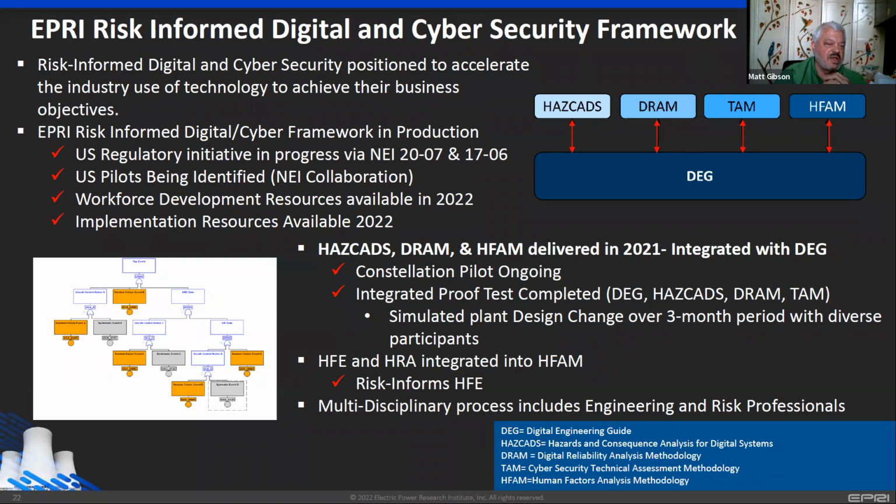Matter of fact, 17-06, which allows IEC 61508's SIL certification process to be used without further analysis in a commercial grade dedication, is progressing.